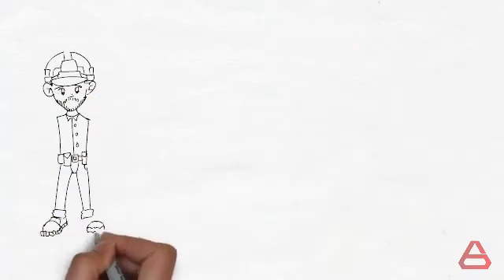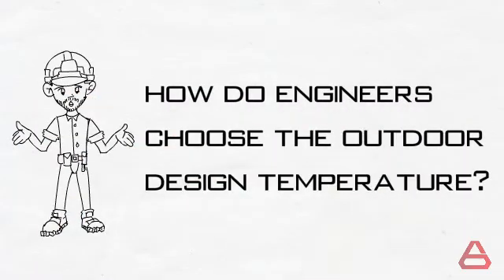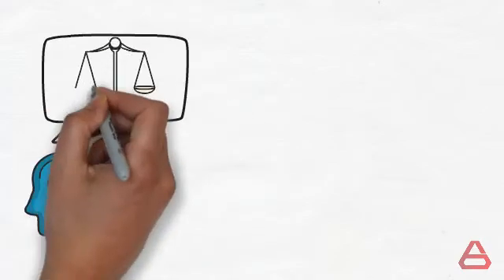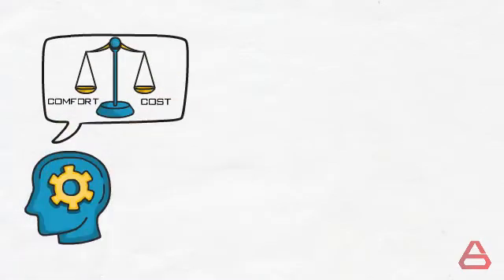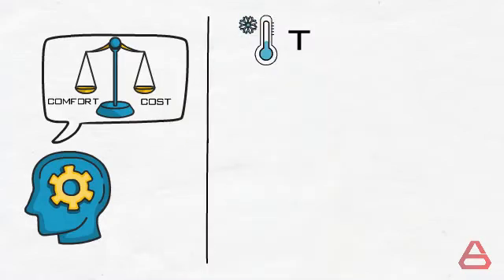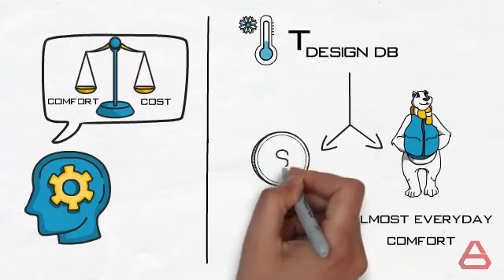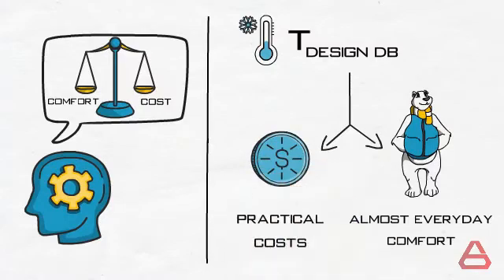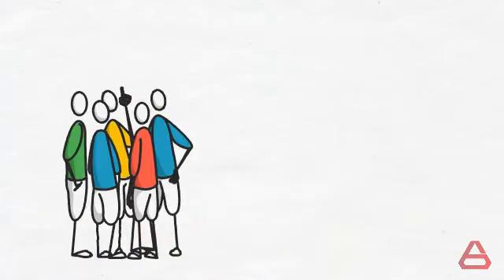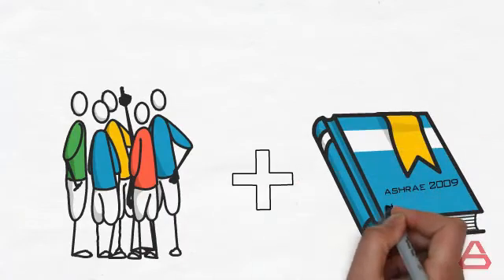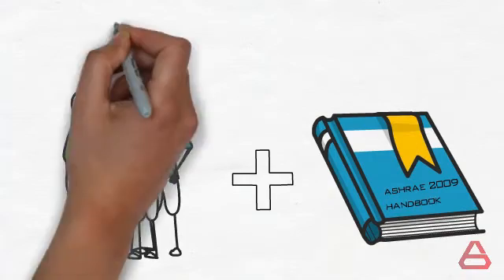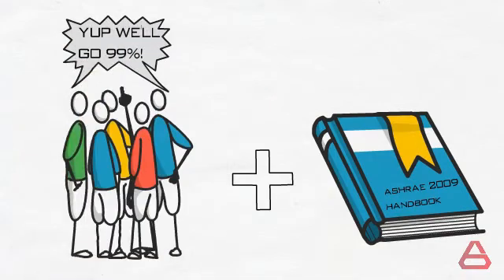So how then do engineers choose the outdoor design temperature? Engineers need a number that would work best from the comfort to cost perspective. The design value should provide almost everyday comfort at practical operation costs. It is common practice between engineers and also as per the ASHRAE 2009 handbook to use the 99% dry bulb design temperature in the winter season.